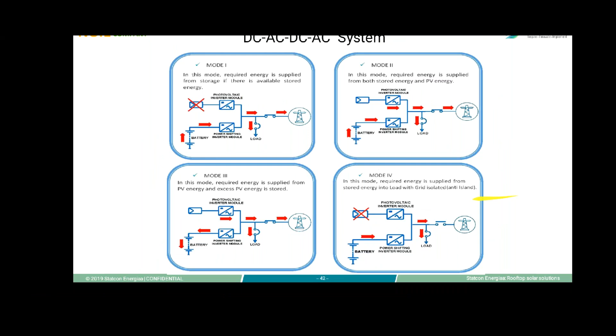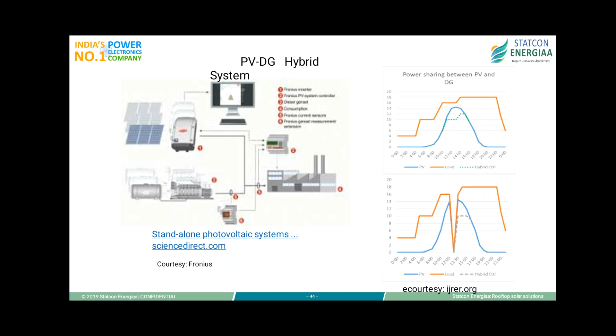Then this is a PV DG hybrid scheme, for which we have taken this slide from Fronius. So this is a PV DG system where whatever is not available from PV can be drawn from the DG side, and it has some problems, like the DG is not running at 30% load, or even if it is running, then we curtail the PV, which is really a sheer wastage of PV power.